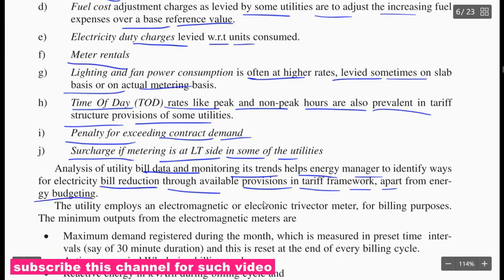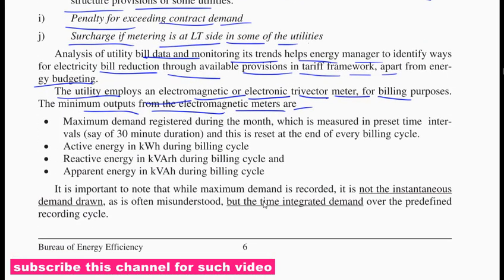And apart from energy budgeting, the utility employs an electromagnetic or electronic trivector meter. For billing purposes, the main outputs from the electromagnetic meter are: maximum demand registered during the month, which is metered in a preset time interval and is reset at the end of every billing cycle.